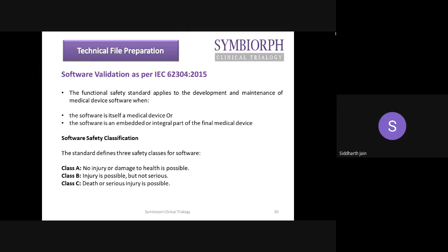Further moving on, there's also a requirement if you are a manufacturer of software, because standalone software or software which is integrated into medical devices is also considered a medical device. So you have to fulfill the requirement of IEC 62304:2015, and you have to classify your products as class A, B, or C depending upon the risk. Class A is no injury or damage to health. Class B is injury is possible but not serious. Class C is death or serious injury is possible. So depending upon the class, you have to validate your software as per the requirements of 62304:2015. Next slide, please.